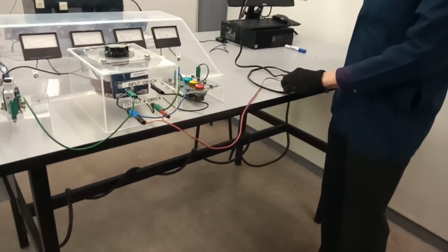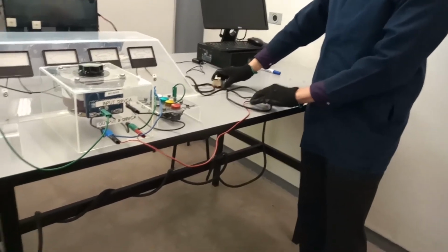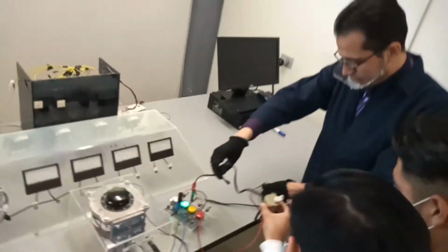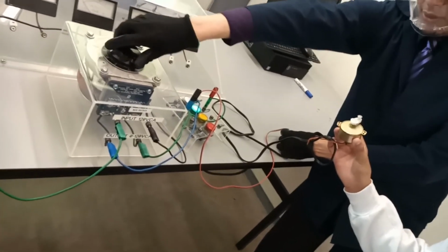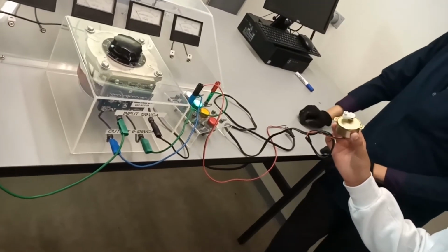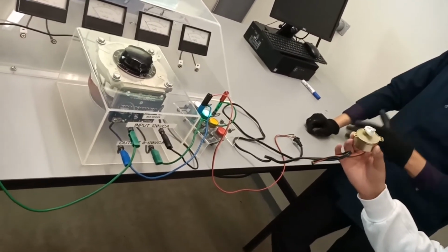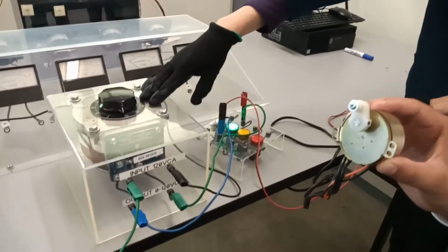The thermomagnetic switch was connected to the line and the output of it was connected to the rheostat. The output of the rheostat was connected to the motor and at the same time to an indicator light. As the rheostat works similar to a potentiometer, according to the position, a different value of voltage was sent to the output, which for this implementation was a rotating motor. There was an initial position in which the rheostat needed to be in order to start moving the rotor.